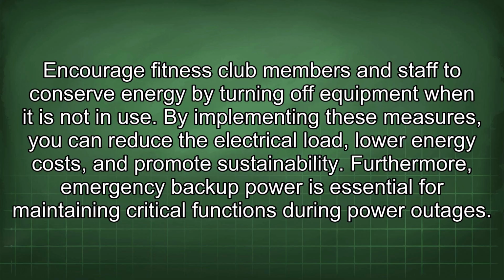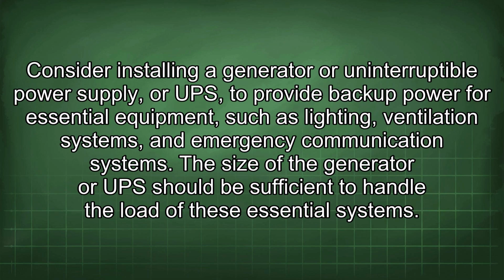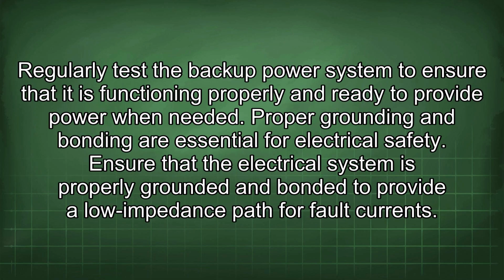Furthermore, emergency backup power is essential for maintaining critical functions during power outages. Consider installing a generator or uninterruptible power supply, or UPS, to provide backup power for essential equipment such as lighting, ventilation systems, and emergency communication systems. The size of the generator or UPS should be sufficient to handle the load of these essential systems. Regularly test the backup power system to ensure that it is functioning properly and ready to provide power when needed.